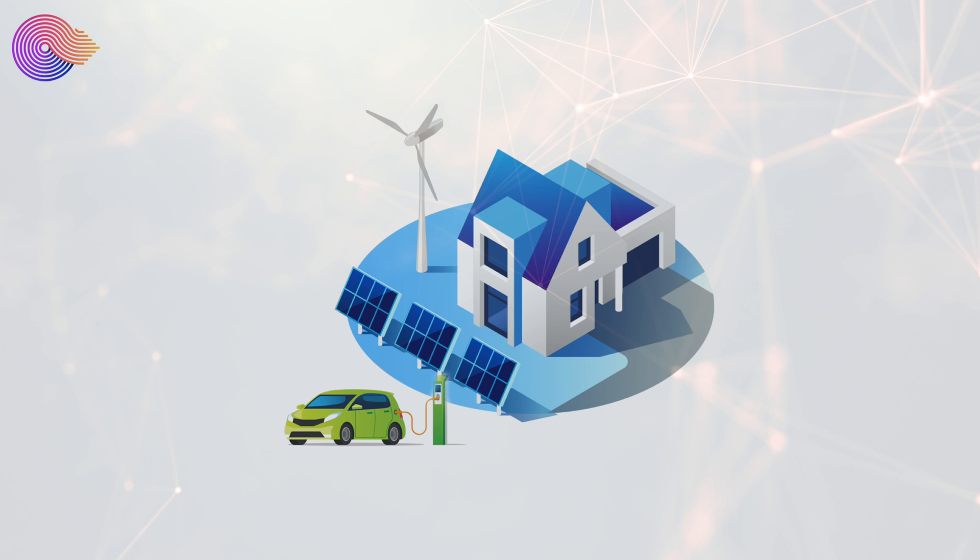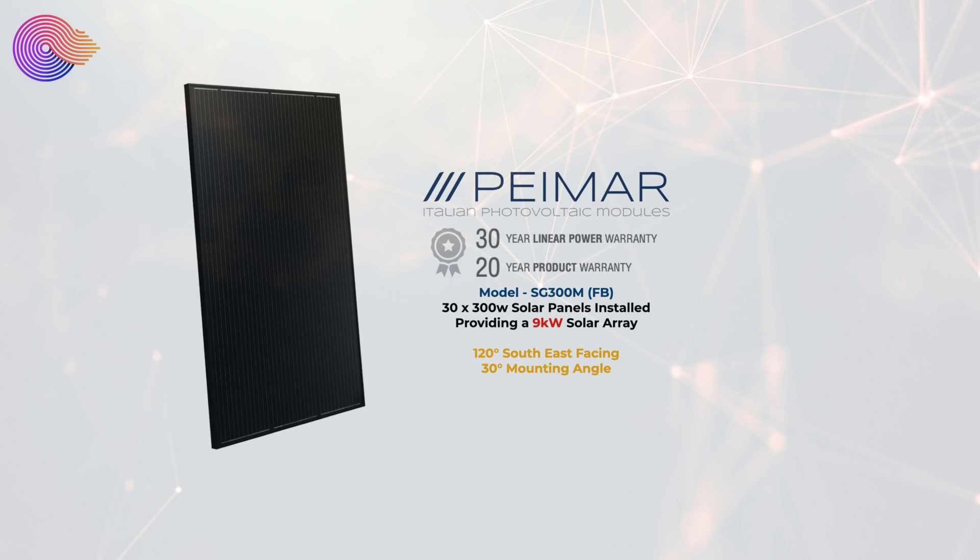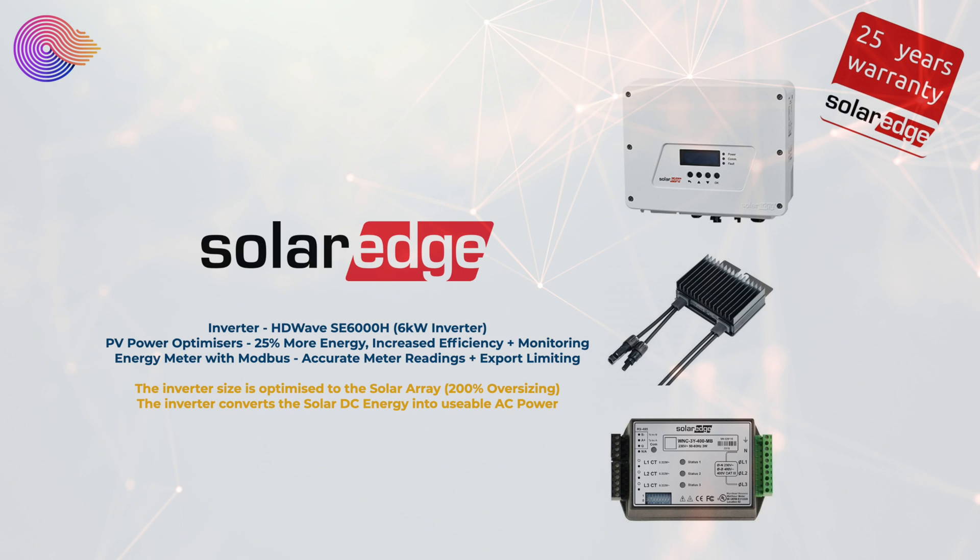If you haven't seen our solar house setup, here's a quick overview. On the main house we have 30 Peimar solar panels, each 300 watts, giving us a 9 kilowatt solar array. These are mounted on the roof at a 30-degree angle facing 120 degrees southeast for good sun collection throughout the day. On the back of each panel is a SolarEdge PV power optimizer for increased efficiency and individual panel monitoring, all connecting back to a SolarEdge 6 kilowatt HD Wave inverter, plus the SolarEdge energy meter with Modbus for accurate readings and export limiting.